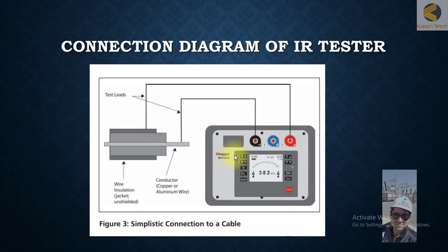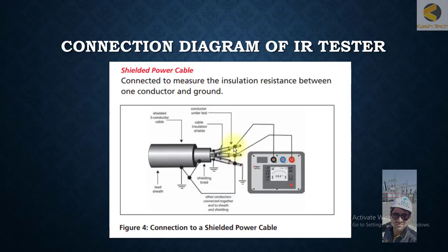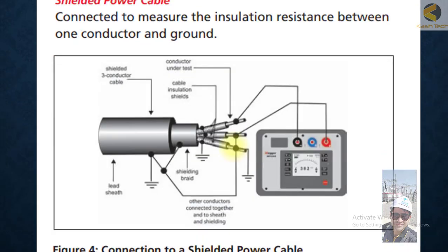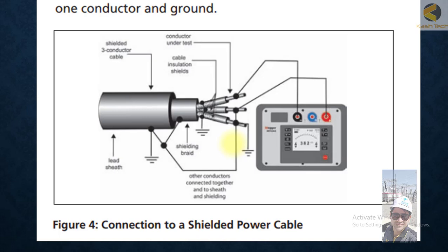This is another example—testing a shielded power cable. The difference here is that with a shielded three-conductor cable, the shield is also part of the object under test and is connected to the black terminal.